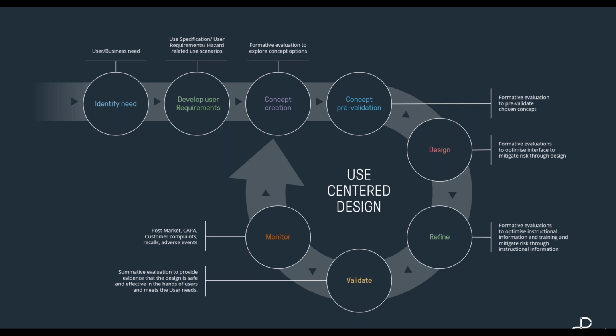which may or may not be needed, depending on the complexity of the device. But that in itself, while we haven't spoken about it so far, is an inherent part of the interface, because it is a piece of information or instruction that enables that interface to be used safely and effectively. Finally is the validation, which is often the key aspect for the regulatory submission, which really at that point, it's just about generating the data to show the interface is safe.